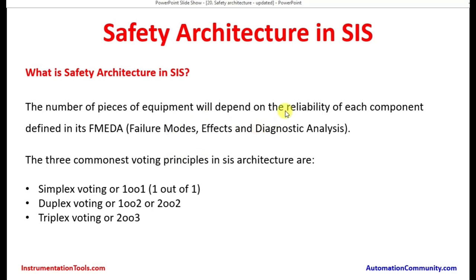As explained in an earlier presentation, these are detailed terminologies which students need to learn when going into a detailed technical training course. The common voting principles in SIS architecture are simplex voting or one-out-of-one, duplex voting which can be one-out-of-two or two-out-of-two, and triplex voting which is two-out-of-three.